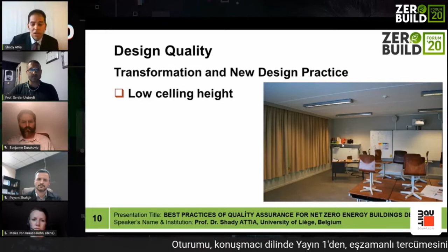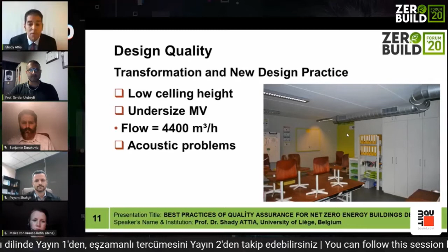There's undersizing of mechanical ventilation systems and ducts, underestimating the importance of sufficient flow rates to assure air quality in buildings. Under the pressure of energy efficiency, we jeopardize thermal comfort in many cases, and acoustic problems are also associated with the new installation of fully mechanically ventilated net zero energy buildings.